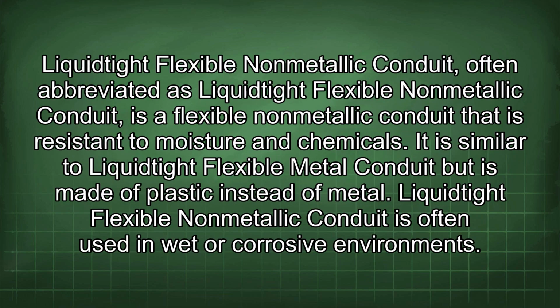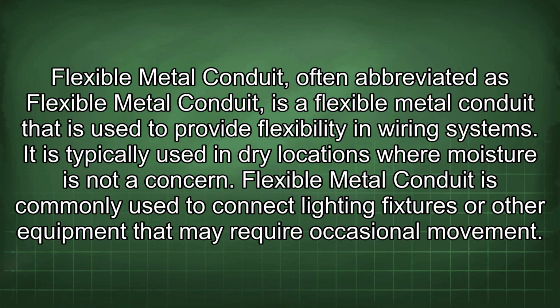Liquid-tight flexible non-metallic conduit, often abbreviated as LFNC, is a flexible non-metallic conduit that is resistant to moisture and chemicals. It is similar to liquid-tight flexible metal conduit but is made of plastic instead of metal. Liquid-tight flexible non-metallic conduit is often used in wet or corrosive environments. Flexible metal conduit, often abbreviated as FMC, is a flexible metal conduit that is used to provide flexibility in wiring systems. It is typically used in dry locations where moisture is not a concern. Flexible metal conduit is commonly used to connect lighting fixtures or other equipment that may require occasional movement.